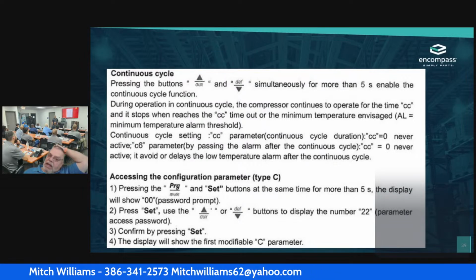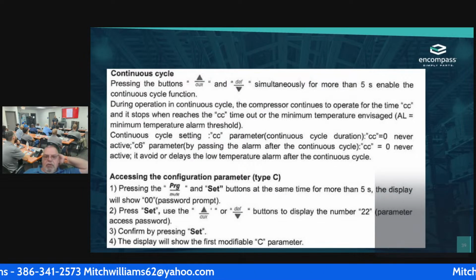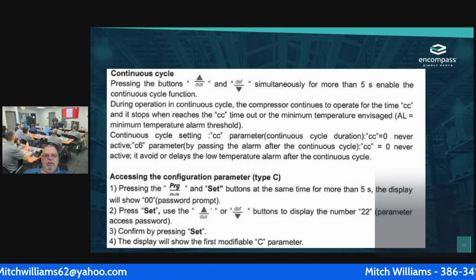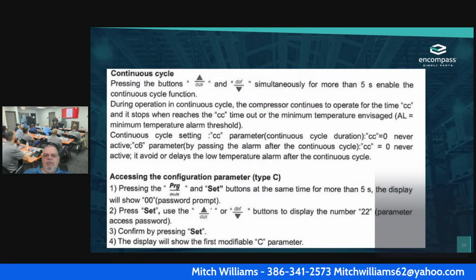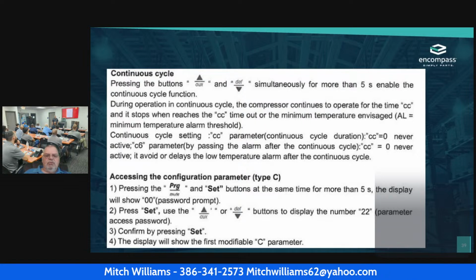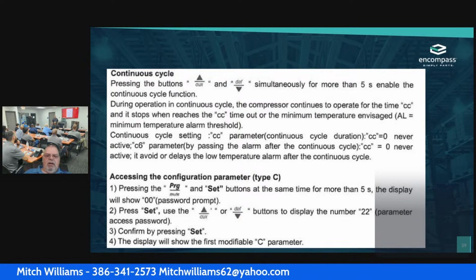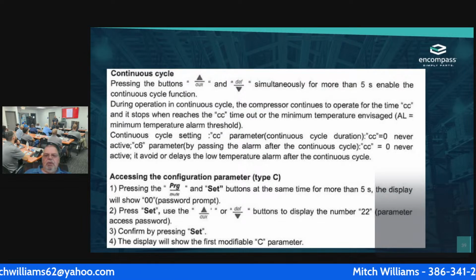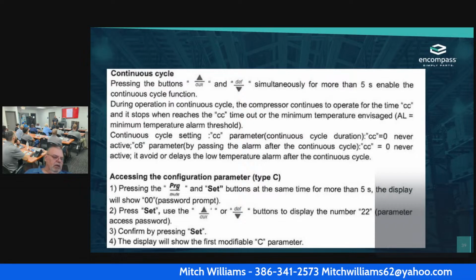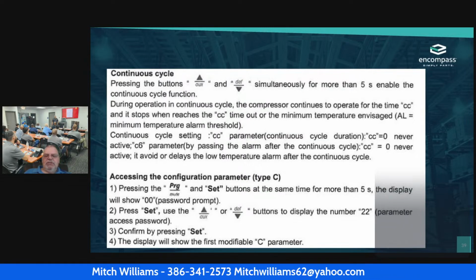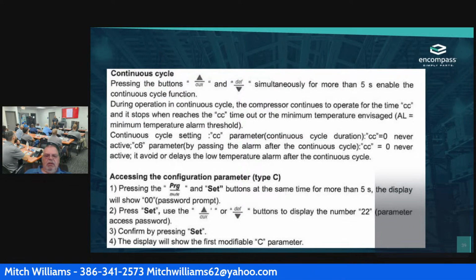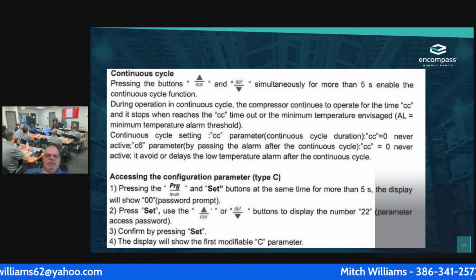Whoever is operating this unit needs to know that we got a low temperature alarm. Okay. Accessing the configuration parameter. This is the C type. I'm going to press the program and the set buttons at the same time for 5 seconds. The display will show 00. That's my prompt for my password. Then I'm going to press the up button until I get to 22. If I overrun it like Nick did, I just press the down button and that will allow me to do it. Once I get 22 on it, I'm going to press the set button.